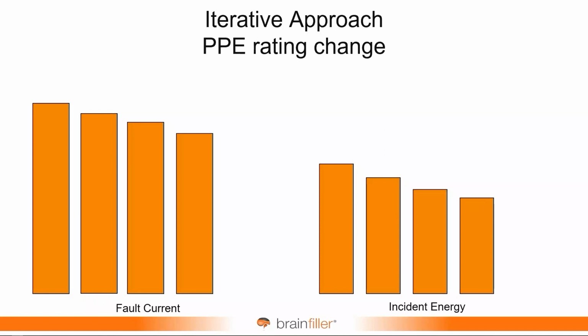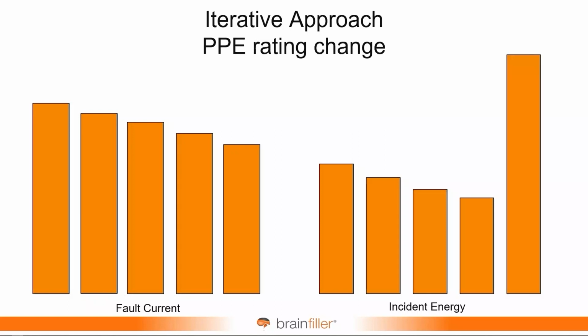And you might think, what's the point of this? What's going to happen is you're going to reduce it one step too many, and you're going to see the incident energy make a very large increase. What you've done is you've defined a range of fault currents where the PPE that you want to use is acceptable, and you've identified how low this can go before you start to have trouble with device operation. Not a perfect answer, but at least it'll give you a range.